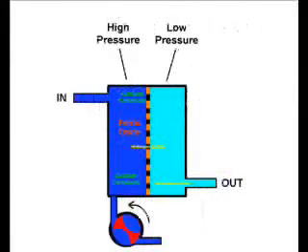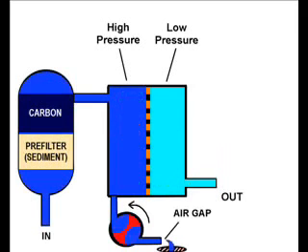If you were to go to your local home improvement center and buy a residential under the counter RO system, you'd likely see three containers or jars. We've already discussed the center compartment, which is the RO compartment, but ahead of that in the lead position is usually a pre-filter and carbon filter combination. The pre-filter is used to mechanically screen large particulates to protect the membrane from large matter, and then the carbon is used to take out any residual chlorine, because chlorine will affect the membrane, it will destroy it, it will eat it up. That's usually in the lead position.